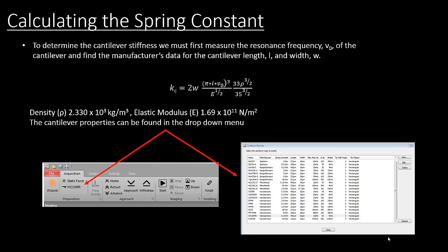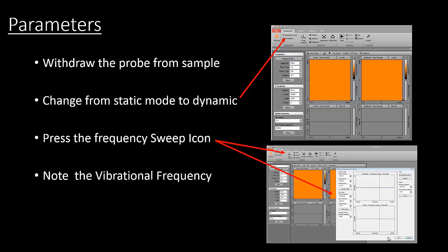Once you have this information, you can input it into the equation below. Values for density and elastic modulus are also provided on this slide. To find information about the cantilever, you must go to the acquisition bar and select the cantilever icon. Here you can scroll through the information until you find your cantilever and record its data. To find the resonance frequency, you first need to withdraw the probe from the sample and change from static mode to dynamic. Then you will press the frequency sweep icon and take note of the vibrational frequency.